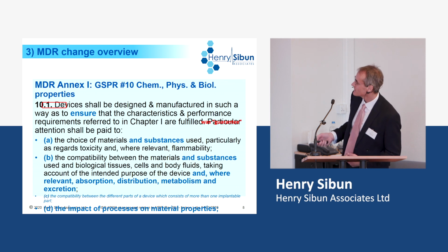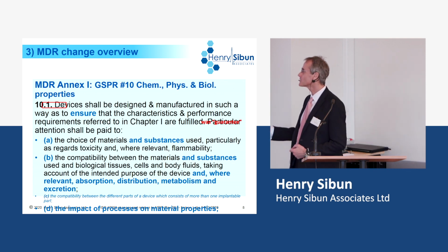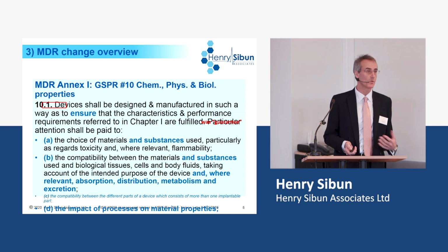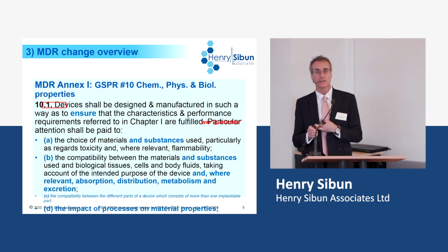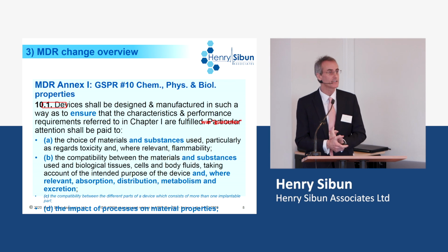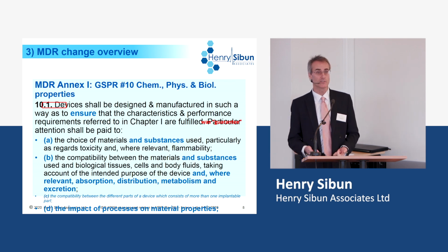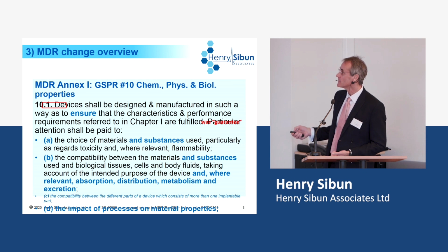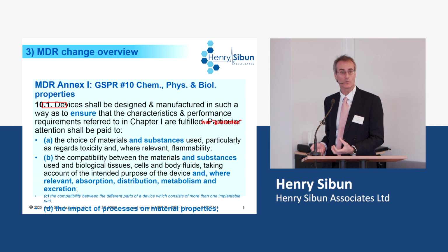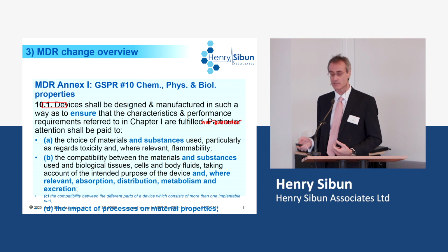Sorry, these have grown a little bit. The last point is the impact of processes on material properties. Again, that was not in the Medical Device Directive, but it was in the 10993, so that's again nothing new. If you think about, in particular, injection molding, extrusion, chemical bonding, sterilization by gamma rays, sterilization by ethylene oxide, all of these have an impact on the materials. So it's not just about understanding the chemistry of the raw material you buy, but understanding the chemistry as to what you've made through the manufacturing processes. Nothing new, but it's specifically stated now in the regulation.